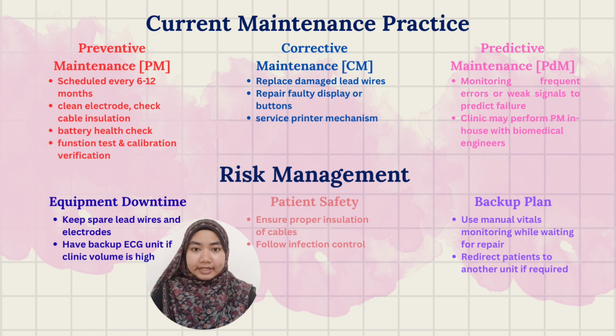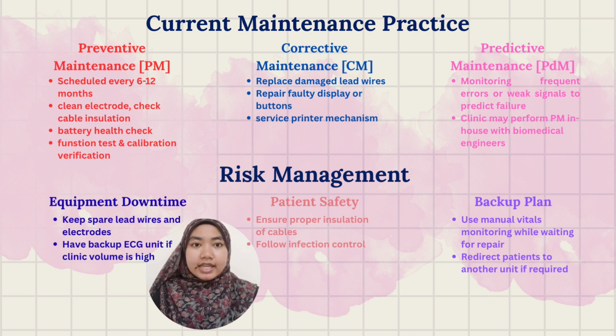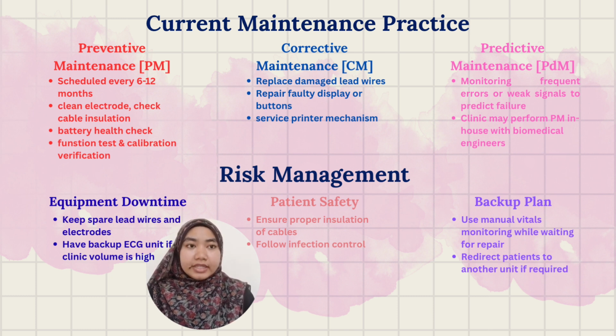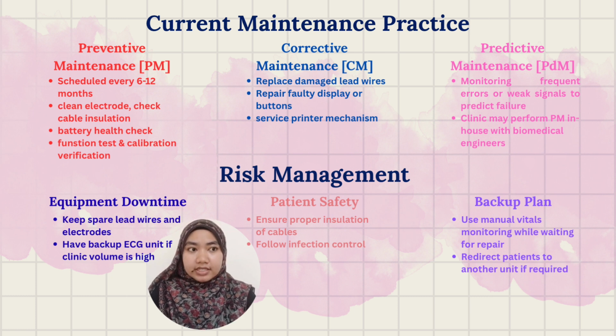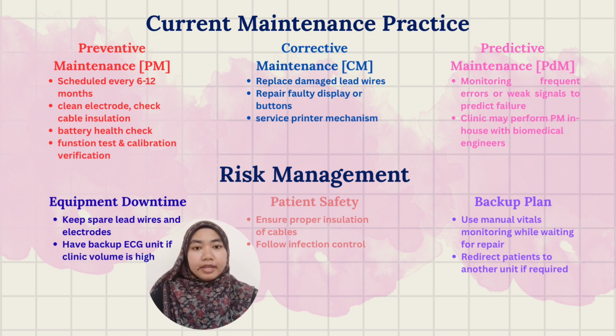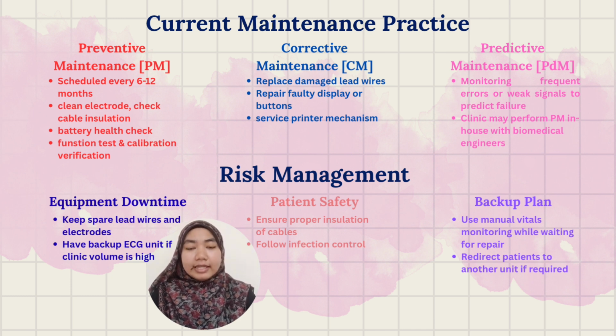Now let's move to current maintenance practice. First, preventive maintenance, which is scheduled every 6 to 12 months. It includes cleaning electrodes, checking cable insulation, battery health check, and function test and calibration verification. Second, for corrective maintenance, we replace damaged lead wires, repair a faulty display or button, and service the printer mechanism. The last one is predictive maintenance, where we monitor frequent errors or weak signals to predict failure. The clinic may perform preventive maintenance in-house with biomedical engineers.